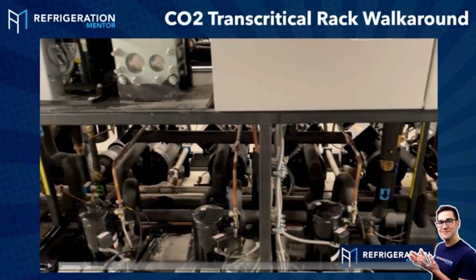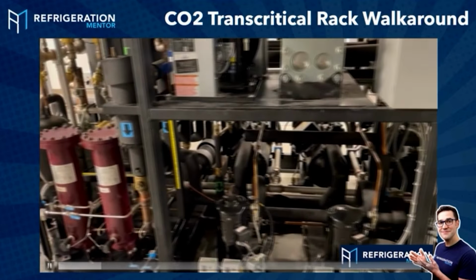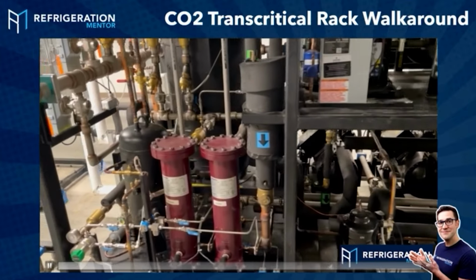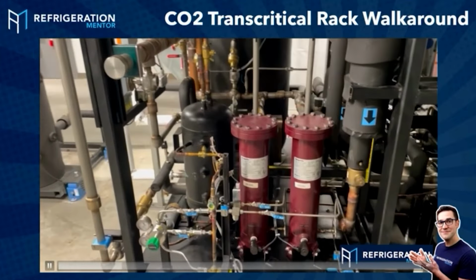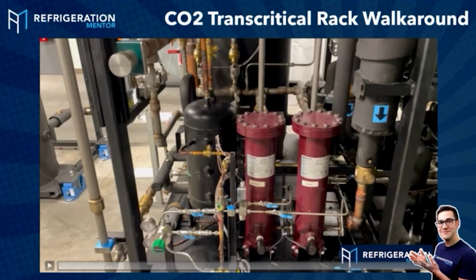No, right? Okay, so we got two fixed. This is the low temp side of this rack, and then we got a digital compressor on there. So digital compressor is a form of capacity control. Next step, we get to this point. This here is the oil management system. So all of you that work on supermarket racks, you will see some type of oil management system. This makes sure the oil stays at the compressors.